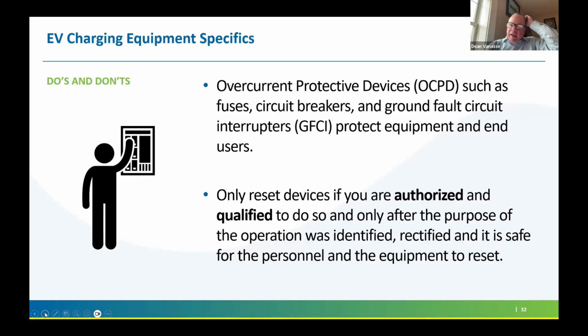You can only reset a protective device if you're authorized and qualified to do so, at the direction of your employer. If you've been trained and can discern the difference between an overload and a fault condition, and how to rectify those conditions, then as a qualified person you could reset that device. But if you're not qualified and authorized, you need to get someone who is knowledgeable, qualified, and authorized to investigate the issue before that protective device is reset.